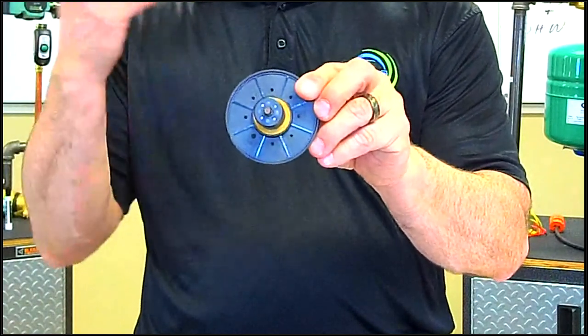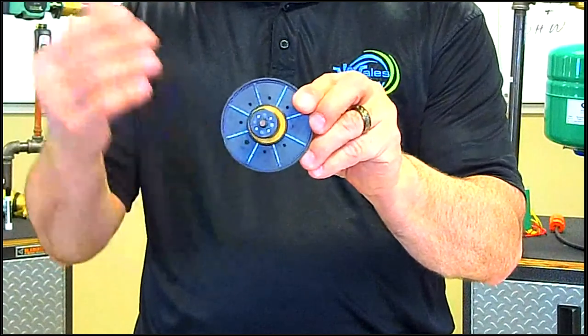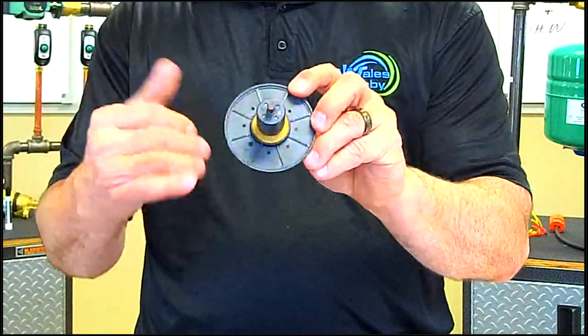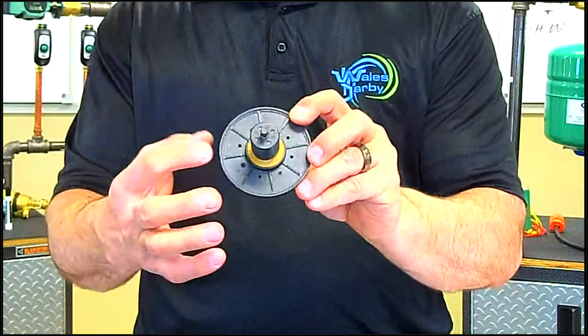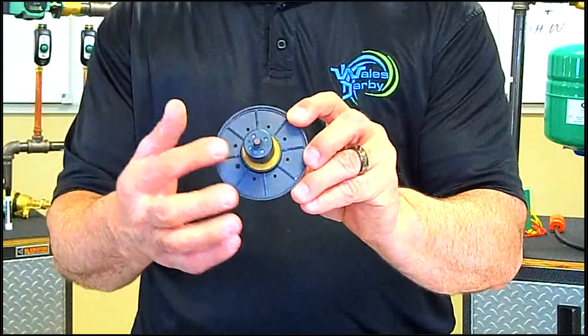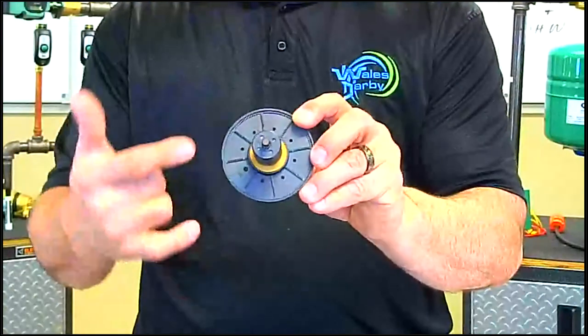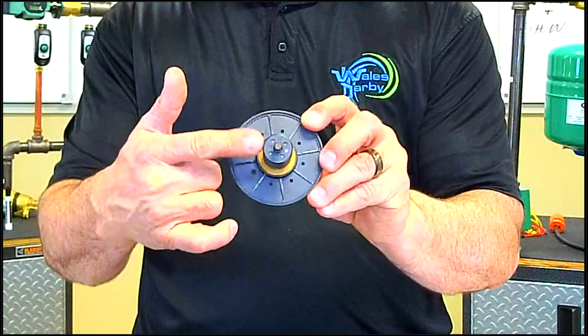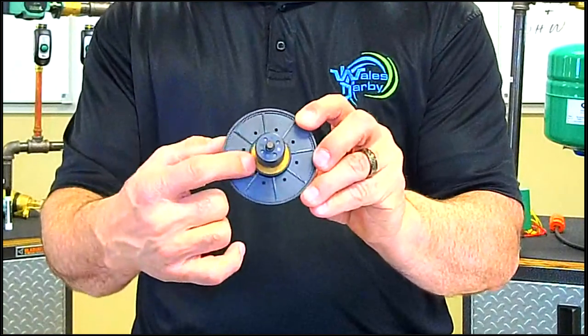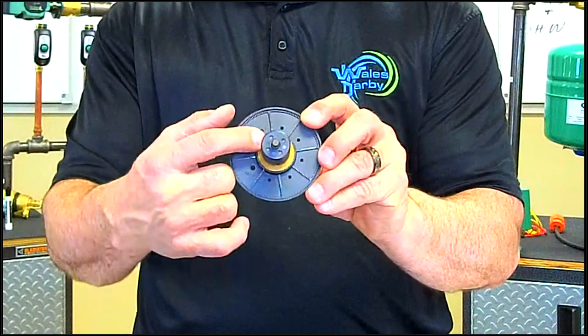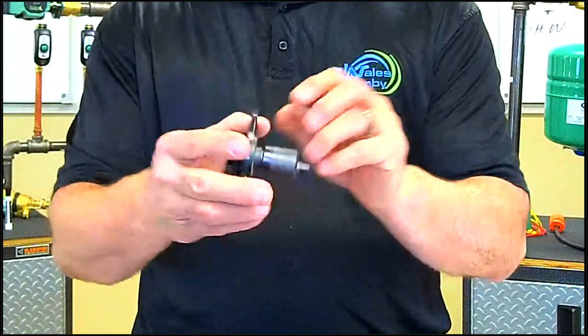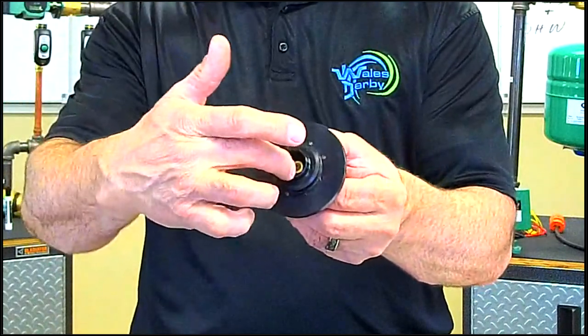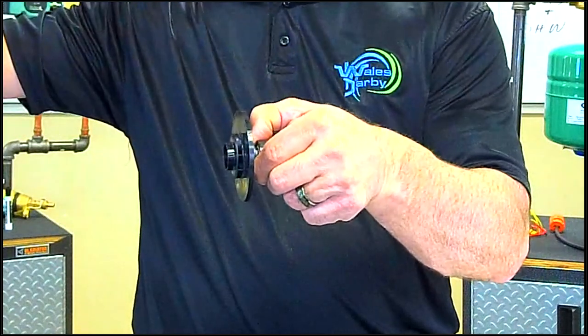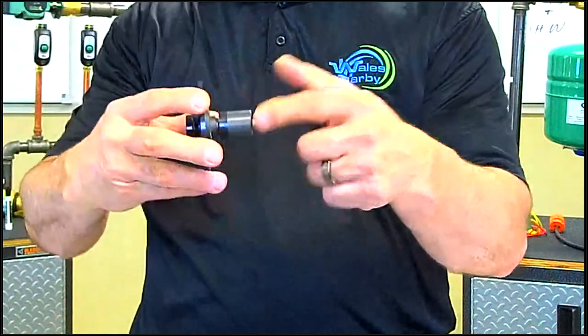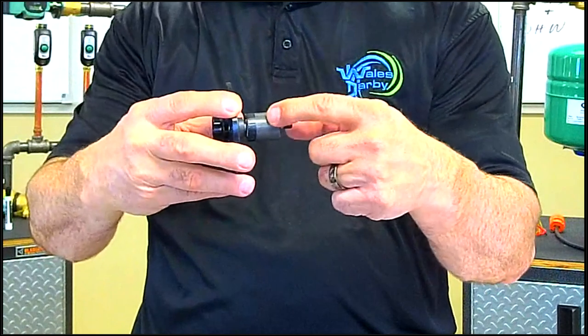Black iron oxide is found in all of our heating systems from metallic pipe breaking down and floating around within the system. What we do to keep that black iron oxide, which is metallic, from attaching itself to the permanent magnet rotor is we put this bio barrier there. And that bio barrier, when the water comes through the eye, becomes a barrier to keep all that black iron oxide out in the system, not allowing it to get into the rotors.